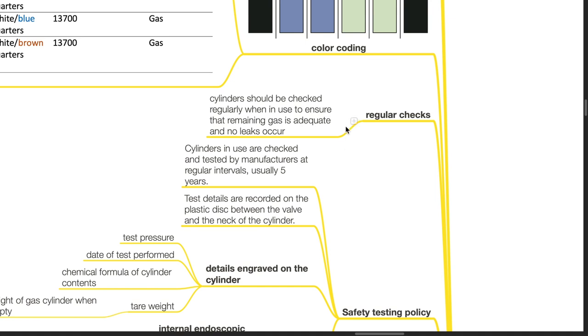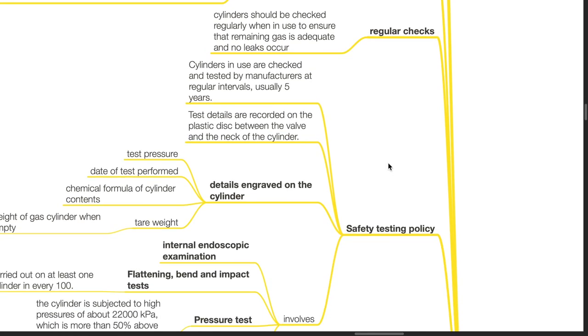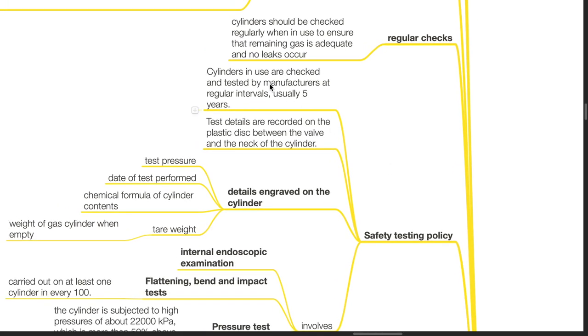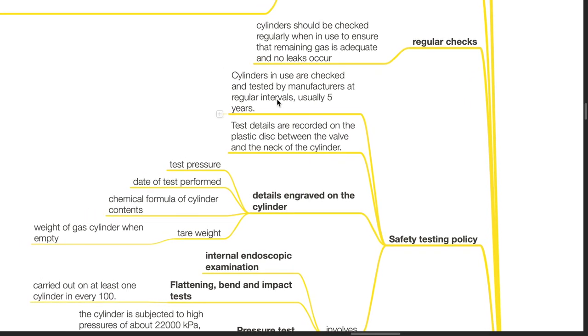Regular checks: Cylinders should be checked regularly when in use to ensure that remaining gas is adequate and no leaks occur. Safety testing policy: Cylinders in use are checked and tested by manufacturers at regular intervals, usually 5 years. Test details are recorded on the plastic disc between the valve and the neck of the cylinder.